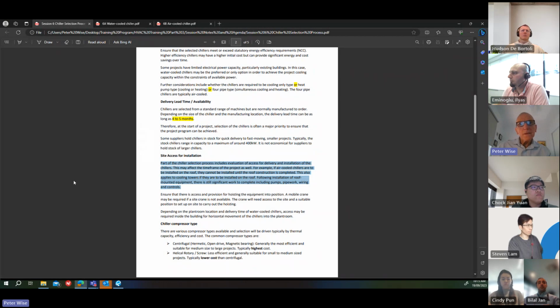Site access for installation. Part of the chiller selection process includes evaluation of access for delivery and installation of the chillers. This may affect the time frame of the project as well. For example, if air-cooled chillers are to be installed on the roof, they can't be installed until the roof construction is completed. So in this case, delivery time of the chillers may not be critical, but completion of the project will be dependent on when the chillers arrive and get installed. So this also applies to cooling towers if they're to be installed on the roof. Following installation of the roof-mounted equipment, there is still a significant amount of work to complete, including the pumps, pipework, wiring and controls, etc. And then all the commissioning.